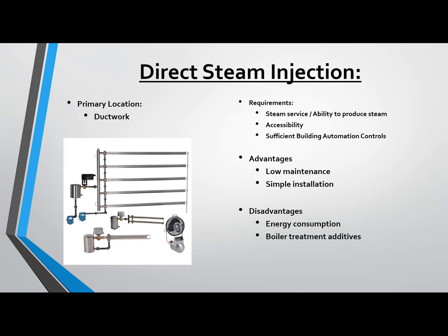Requirements for these: you must have steam service. Obviously, it's a direct steam injection unit, so if you don't have steam service, you're not going to be able to inject steam very easily. And you must have the ability to produce the steam at the capacity that is required. Accessibility, not so much from an ADA standpoint, but from a facility accessibility standpoint of being able to get these installed in the correct location in the ductwork. If it is an existing facility, or if it is a newly designed facility, it's a lot easier to design in that location and make sure facility folks can have the access they need to get to these areas safely to help maintain and perform preventative maintenance on these units.